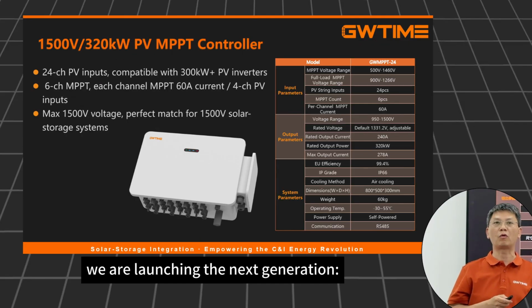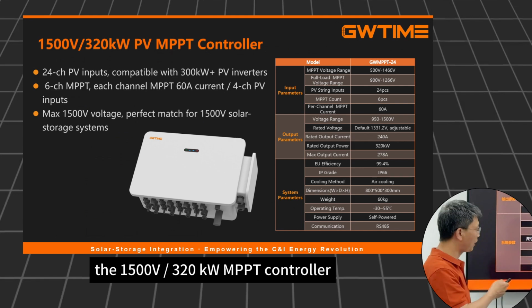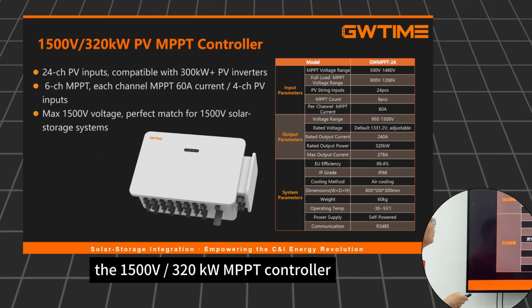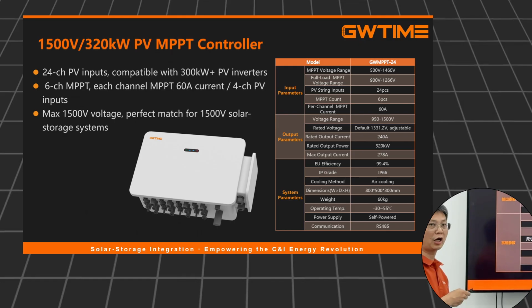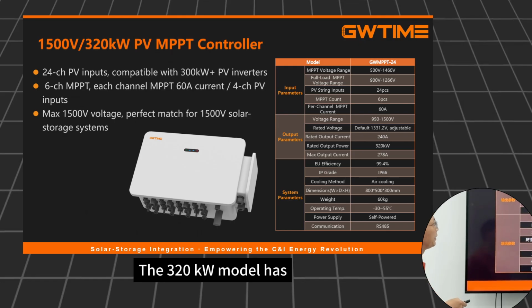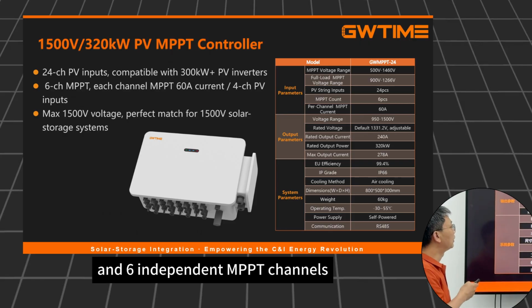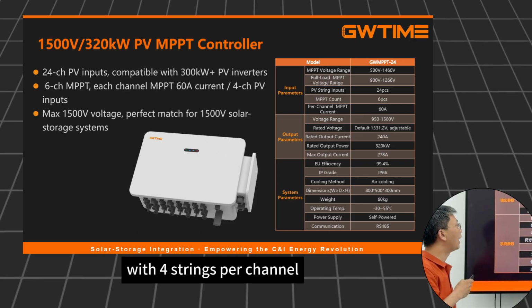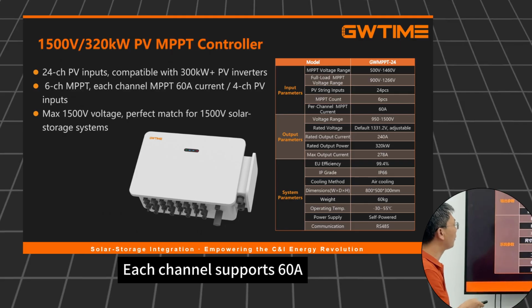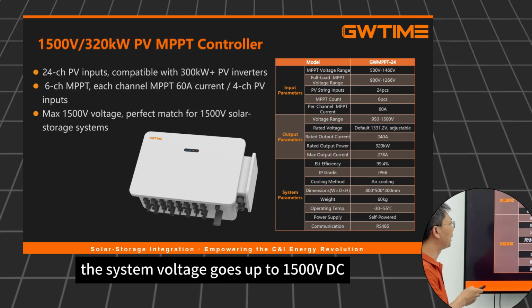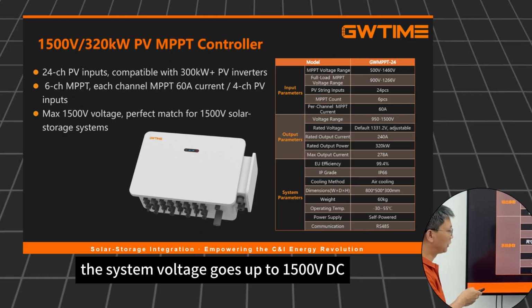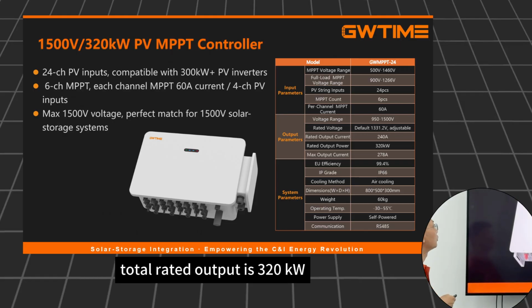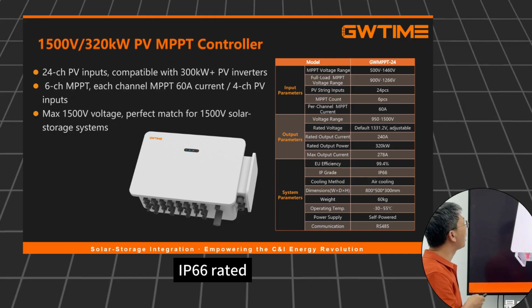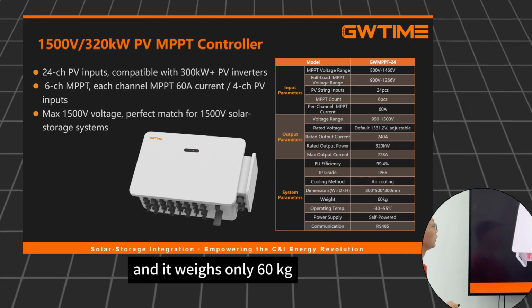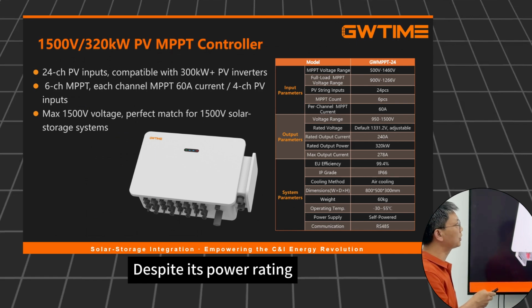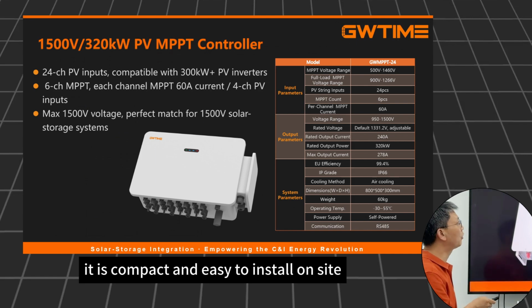Today, we are launching the next generation, the 1500 volts/320 kilowatts MPPT controller. The 320 kilowatt model has 24 PV string inputs and 6 independent MPPT channels with 4 strings per channel. Each channel supports 60 amps. The system voltage goes up to 1500 volts DC. Total rated output is 320 kilowatts, IP66 rated, and it weighs only 60 kilograms. Despite its power rating, it is compact and easy to install on site.